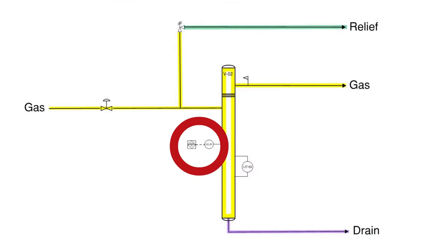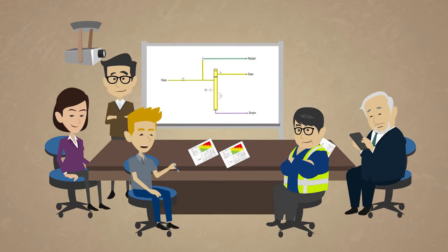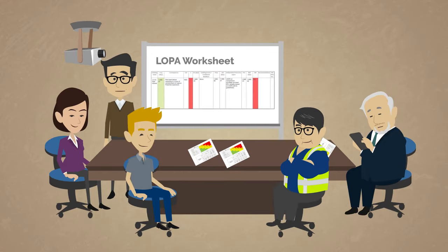There is a high-level shutdown on the suction scrubber of the compressor wired to the compressor's logic solver. If any liquids reach the scrubber, it will trip the compressor before any damage can occur. Excellent.